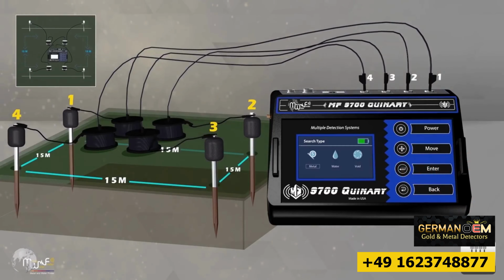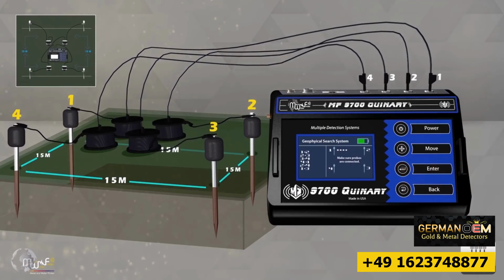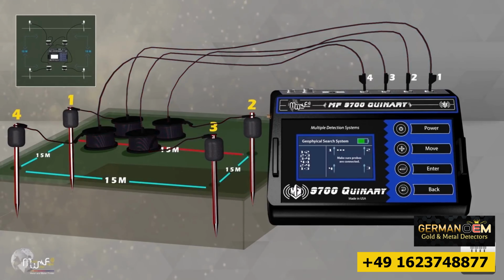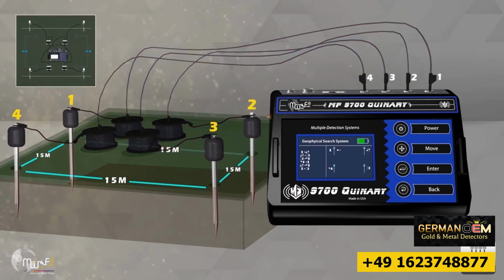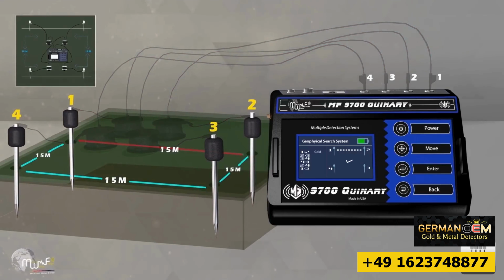Choose the type of target to search for: metal, water, or voids. Click Enter and the device will start searching between the probes. If the connection between the probes is not good or is faulty, a message will appear to make sure that the electrodes are connected properly. Then the device continues scanning, searching through the probes' connection points according to the connection probe numbers. After the device has completed this stage, it identifies the target within the survey area.